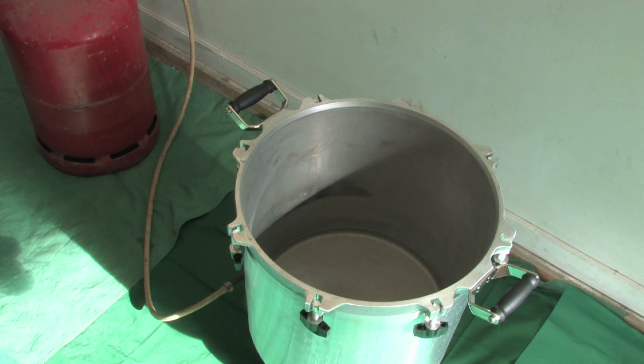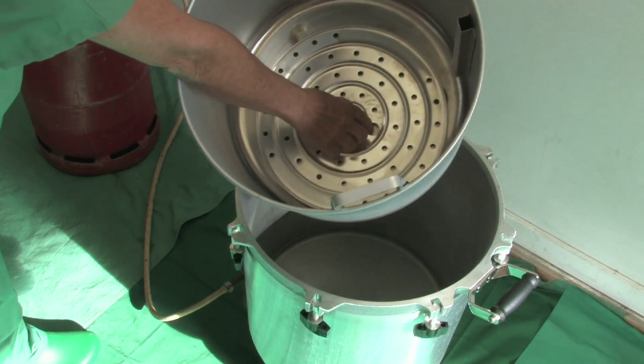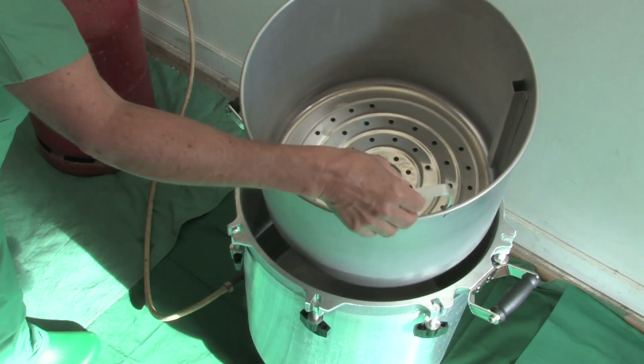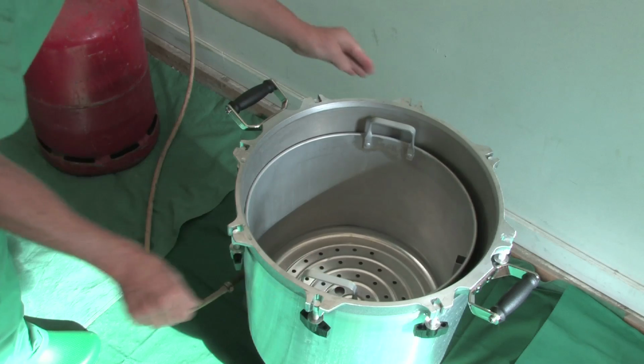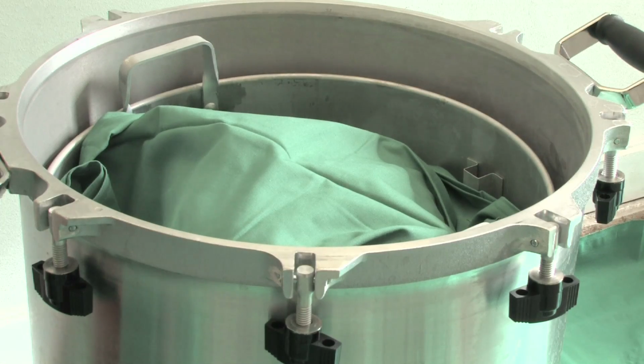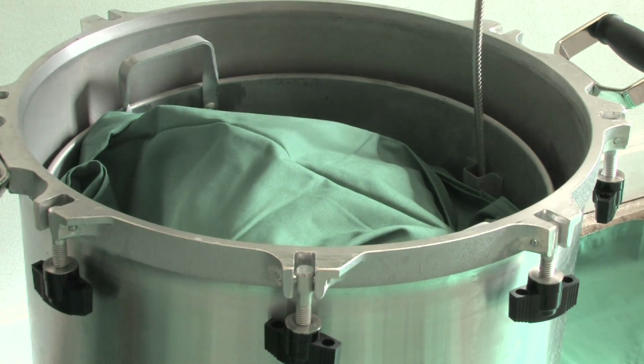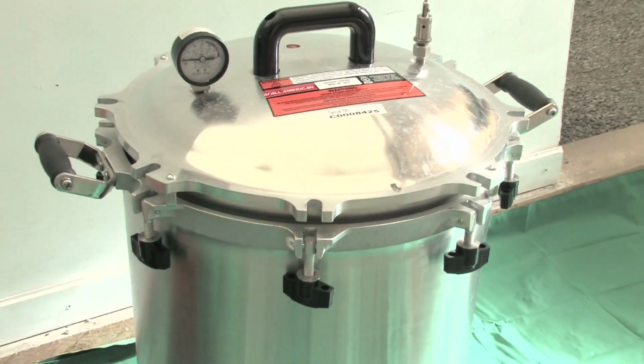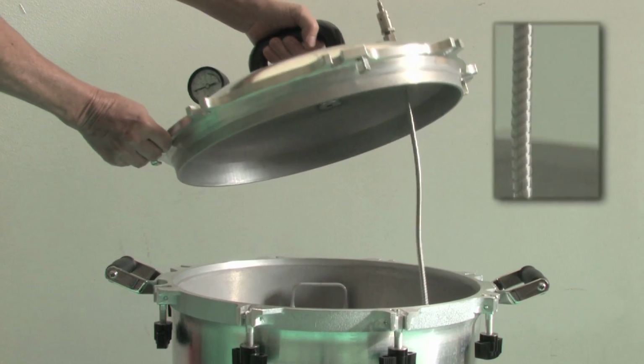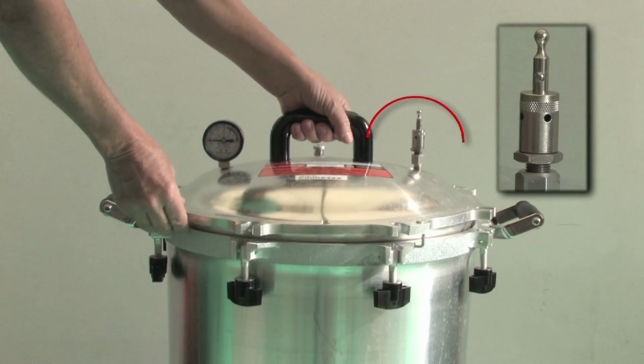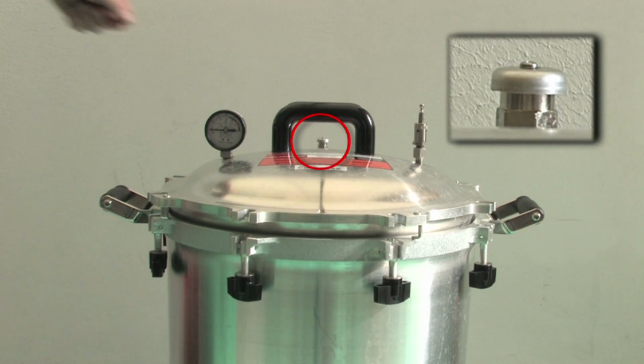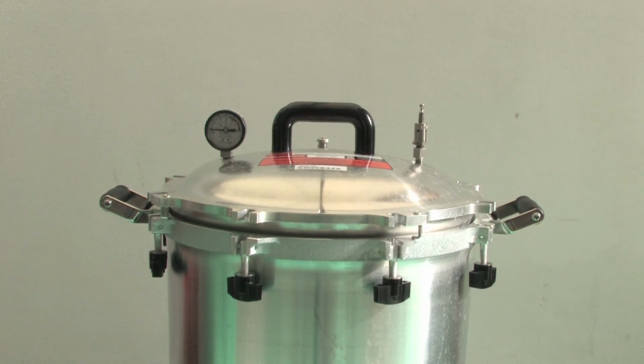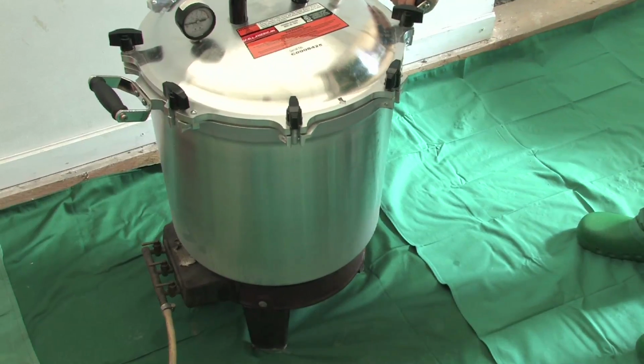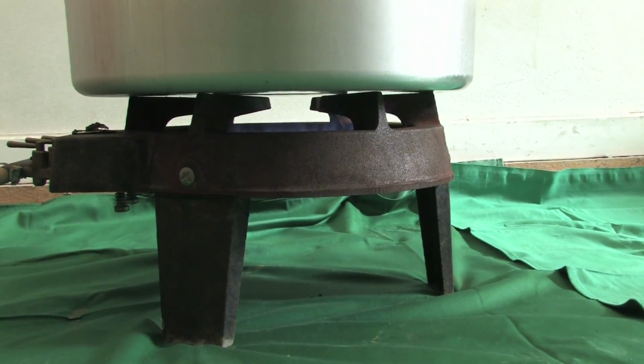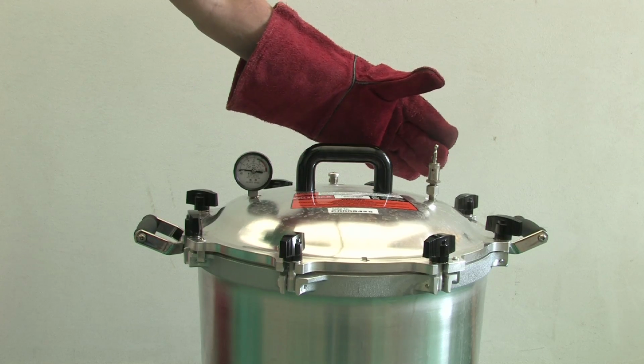It consists of a small volume 39-litre autoclave chamber, a metal basket in which the packs to be sterilized are placed, and a perforated plate that goes in the bottom of the basket to prevent the condensation that accumulates in the bottom of the basket from wetting the packs. The inside of the basket has a guide channel into which the flexible tube used to remove air and steam is inserted. A cover with a handle, a flexible metal tube connected to an exhaust valve for air and steam, a safety valve, and a pressure gauge. This autoclave is not electric. It uses an external energy source, such as a gas ring. Caution: the autoclave must be handled with protective gloves to prevent burns.